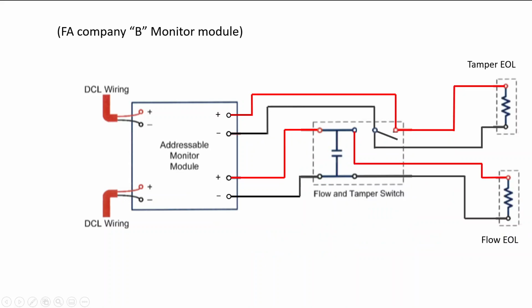This is, let's say, fire alarm manufacturer B, and it's the same application, but the manufacturer requires that we have a separate connection for our flow switch than for our tamper switch, and each of those then having its own independent end-of-line resistor. This is simply to show you that there are different ways it can be done, and it's not going to be assumed that you have to put one or the other in. When you are given the equipment on site and you look at the prints, you'll see one of these two different variations provided, and you'll then look at the manufacturer's wiring instructions to determine exactly how the wiring connections need to take place and what size the end-of-line resistor will need to be.